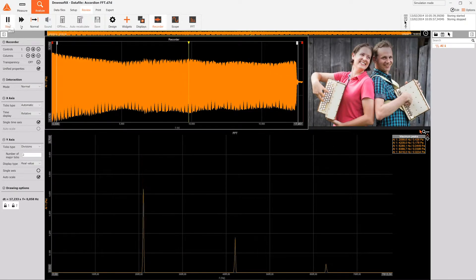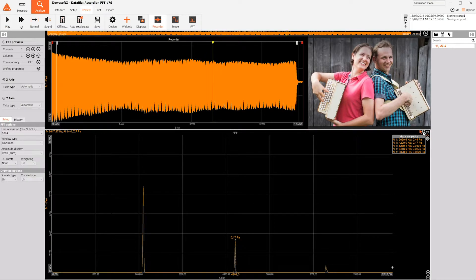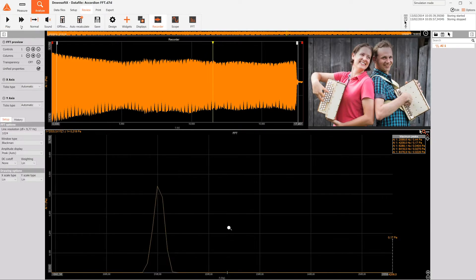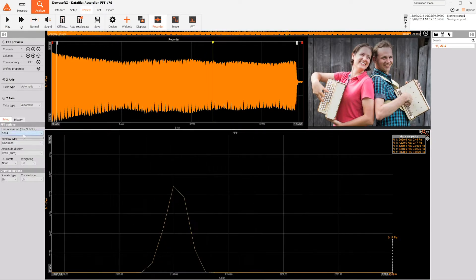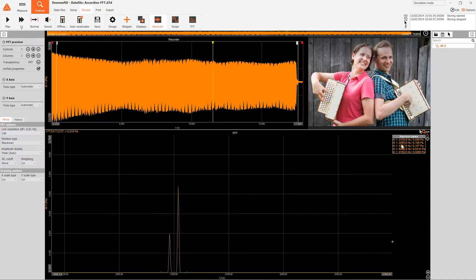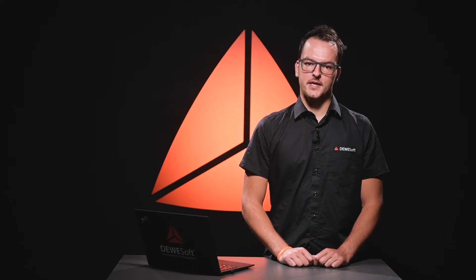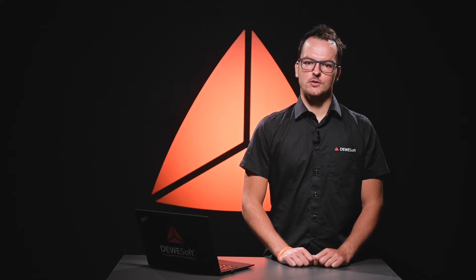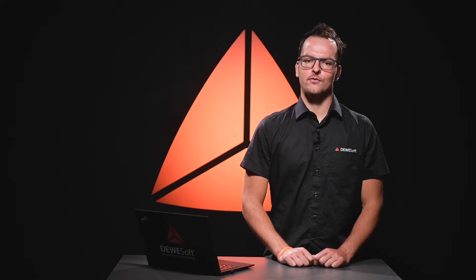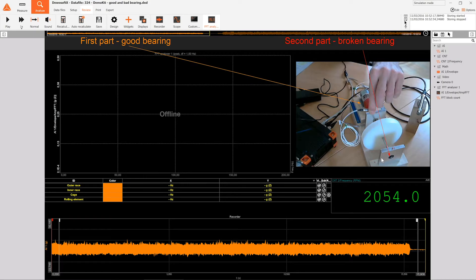Imagine that you are playing an accordion and it's not tuned perfectly. You can always hear a beating signal when you play it. A beating signal is a sum of two closely spaced frequencies. To detect these two peaks in the frequency spectrum, we must have a large number of lines to ensure good resolution at higher frequencies.